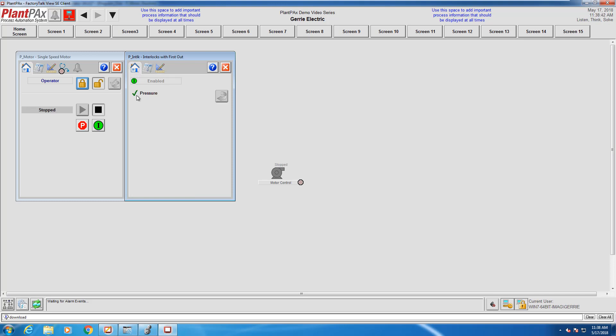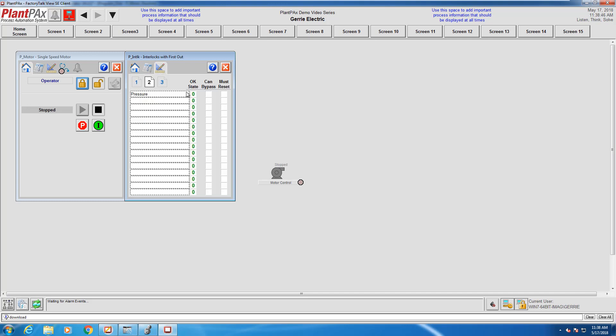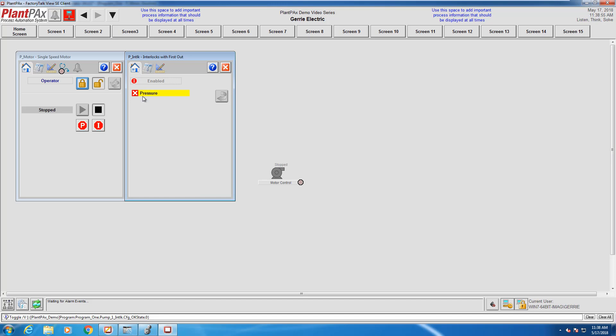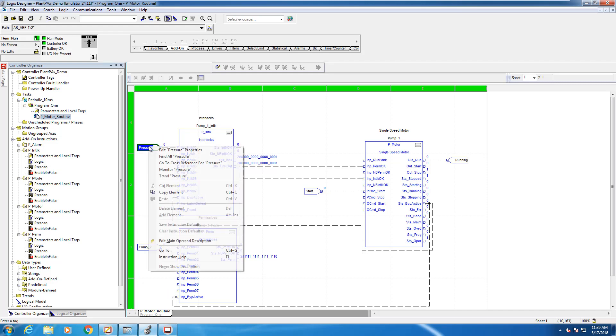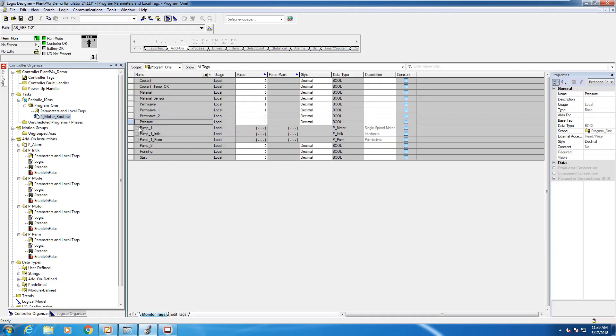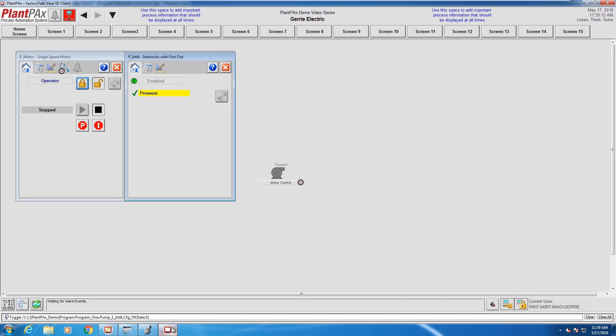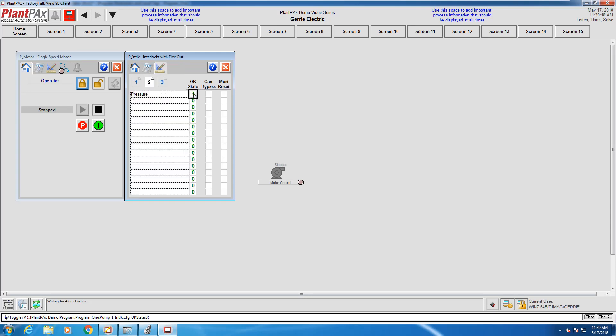We can see here pressure is okay because the okay state is low, which is correct. If we were to change this to okay state is high, when we go back to our home screen we'll see there's a problem with pressure because our pressure state in our PLC is off right now. If we toggle this bit to high, we can see here now pressure is okay because we've set this up so the okay state is high.